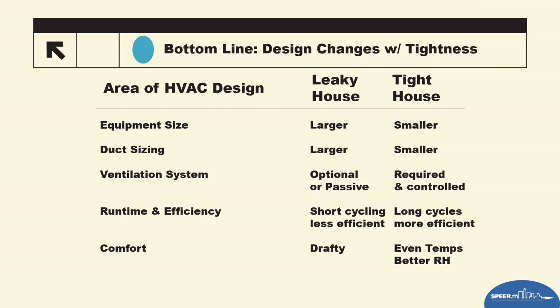Ventilation system: if it's a very leaky house, then it's an option for passive leakage that's happening with infiltration, or uncontrolled infiltration. In a tight house, of course, it's required now, and it also is a controlled way of allowing infiltration inside the building. Runtime and efficiency: if you have a leaky house, most of the time it's short cycling. And then in a tight home, you have much longer cycles that run more efficiently, with better humidity control. And also leaky, of course, if you've been in a leaky house, drafts a lot of times happen, and that's most people's first complaint. But I think I've mentioned it before.